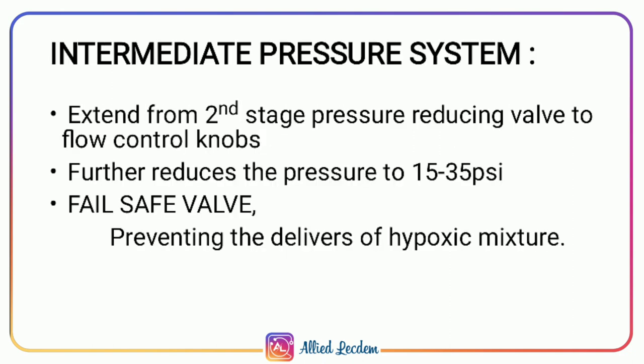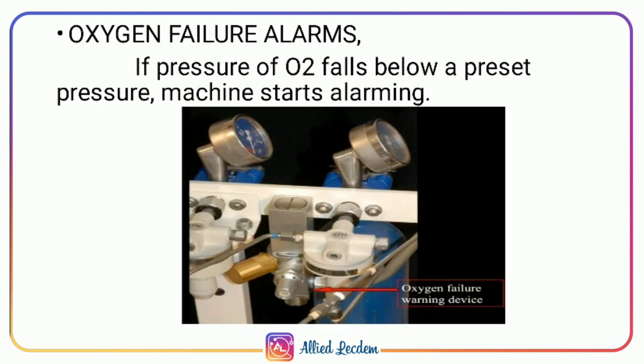The intermediate pressure system extends from the second stage pressure reducing valve to the flow control knob, and further reduces the pressure to 15 to 35 psi. The fail-safe valve prevents the delivery of a hypoxic mixture. The oxygen failure alarm activates if the pressure of oxygen falls below a preset pressure.